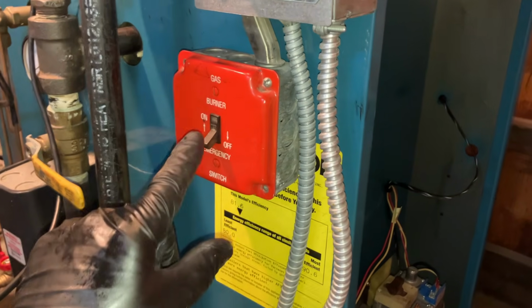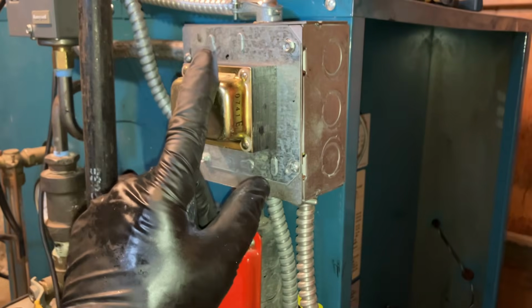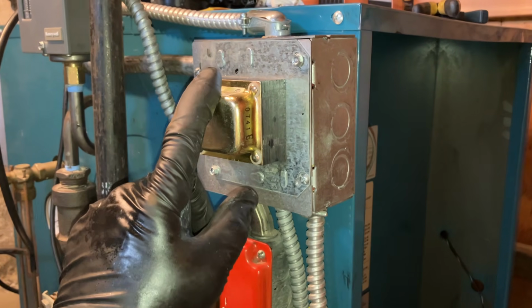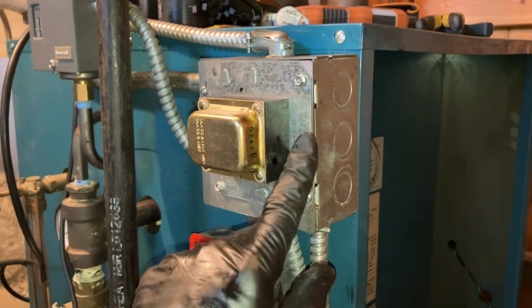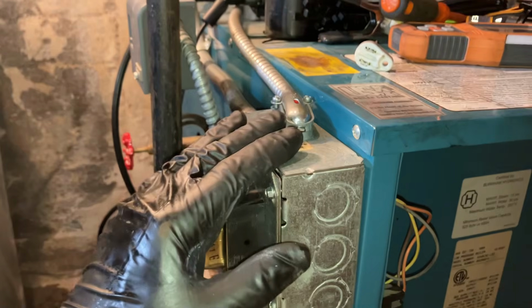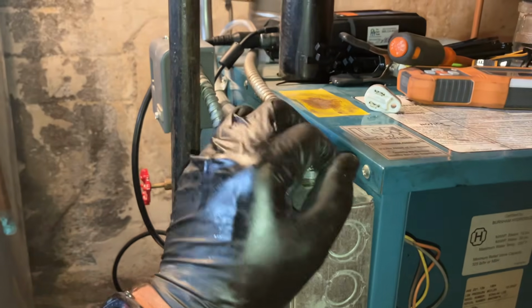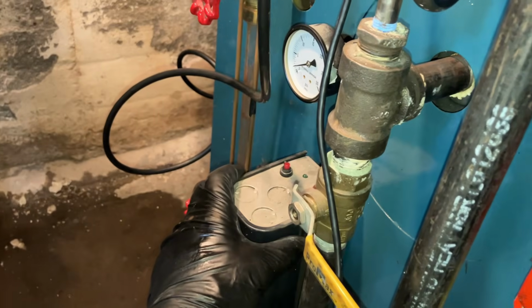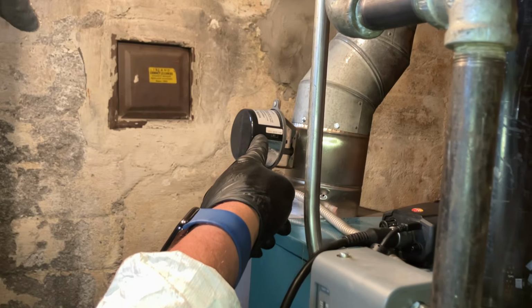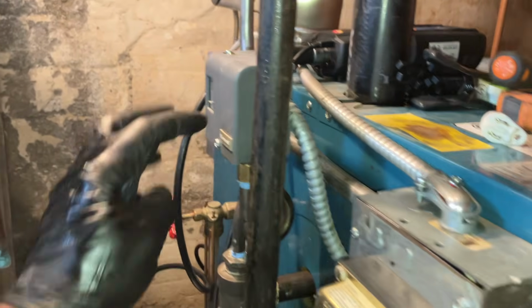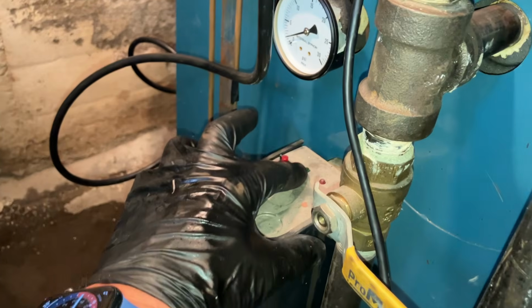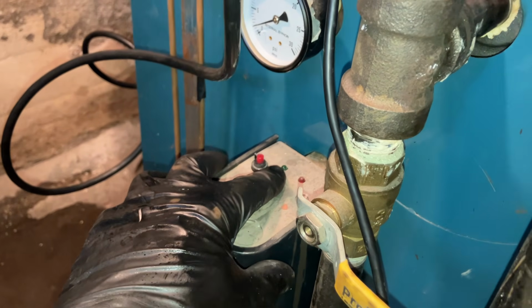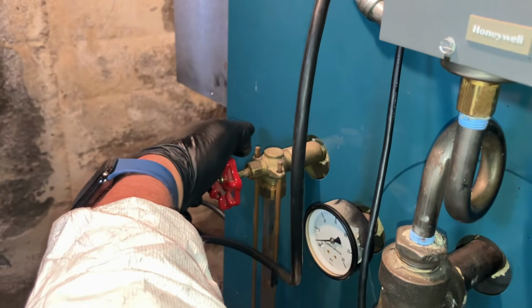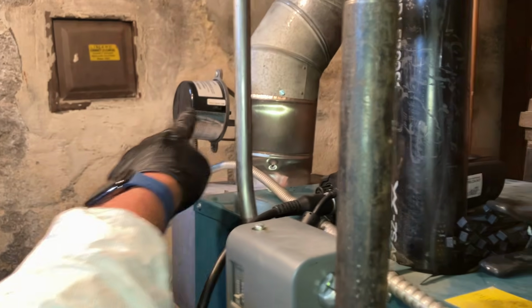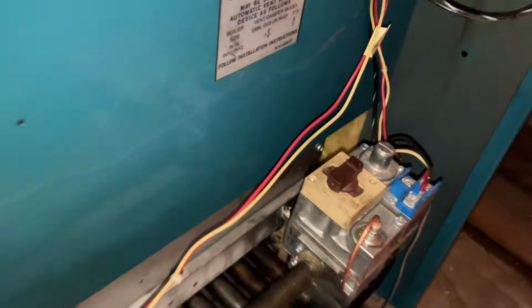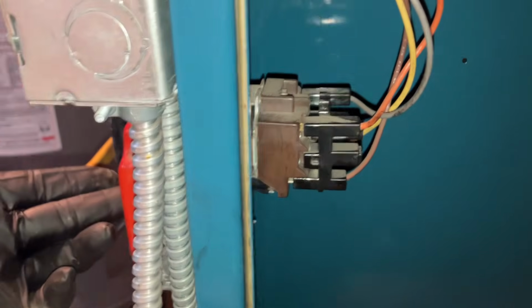All right, now remember, ladies and gentlemen, when we apply power, the transformer is getting 110 volts. It's going to transform that power to 24 volts, powering the boiler circuit and the safety circuit. It's going to send constant power to the low water cutoff, constant power to the automatic vent damper. The safety circuit is the pressure control, the probe, or the sensing of water on the low water cutoff, our spill switch, our vent damper end switch, and our rollout switch. Thermostat still calling, ready for that click.